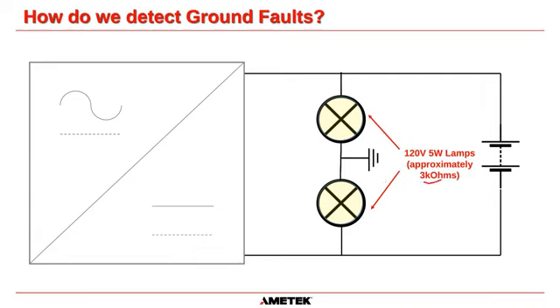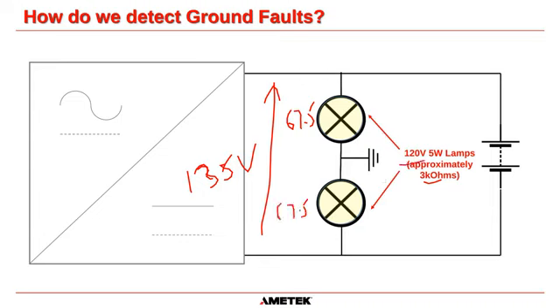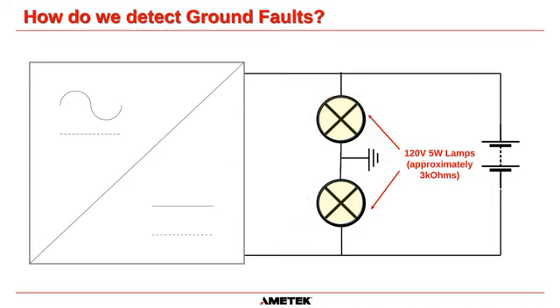Okay? Now, what's going to happen, and I'll explain it on the next screen, is the full system voltage is 135 volts DC. By putting 2 lamps in series and connecting it to ground, we're going to get about 67.5 volts there, 67.5 volts there. Because this is a 120 volt lamp, these lamps are only going to be half lit, dimly lit. But both lamps should be lit the same, because the amount of current flowing through both lamps should be the same, because we have no current flowing to ground.